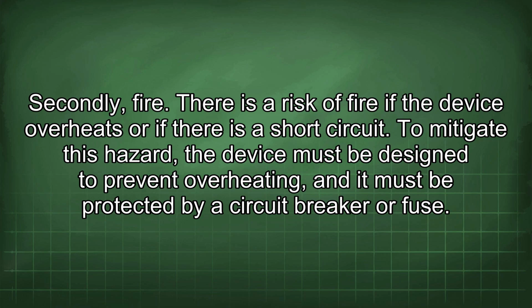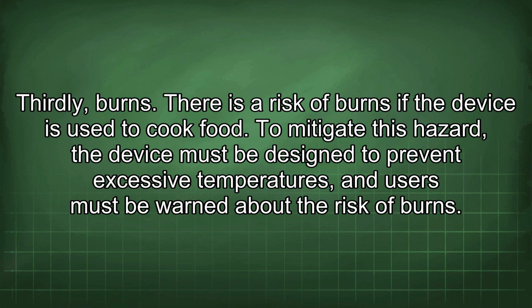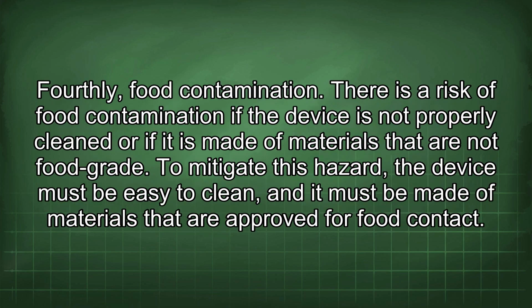Thirdly, burns. There is a risk of burns if the device is used to cook food. To mitigate this hazard, the device must be designed to prevent excessive temperatures and users must be warned about the risk of burns. Fourthly, food contamination. There is a risk of food contamination if the device is not properly cleaned or if it is made of materials that are not food grade. To mitigate this hazard, the device must be easy to clean and it must be made of materials that are approved for food contact.